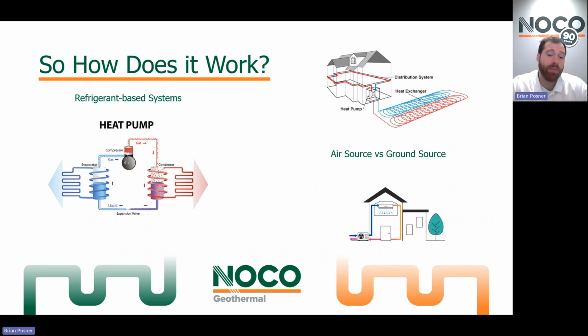Now, with geothermal piping being buried under the frost line, that's the benefit of being at least 4 feet deep, if not deeper, we're in a 55-degree heat sink all year round. So when we want to heat a building, instead of pulling initially from 0 or 10-degree winter air, we can pull from the 55-degree ground. It means we can use warmer refrigerant, and we need to cycle it less often, and overall it uses quite a bit less electricity. One of the main aspects to consider too is that with this piping all being buried under the frost line and no above ground components in this system, it is very unlikely that this system will get shut off by cold temperatures.